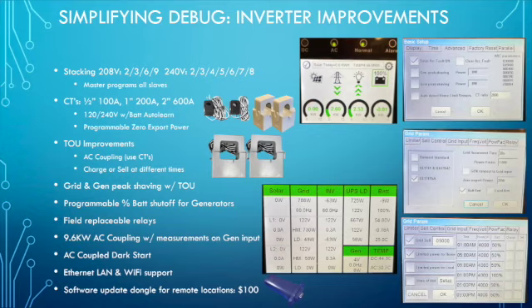So as far as inverter software improvements and other things, we did quite a few developments. We introduced stacking for 240 volt. That's been around for a while, and you can do anywhere from 2 to 8. But you can also stack 208 systems, and you can do 208 with just a single system. However, you won't be able to do all 3 phases, just 2 of the 3. So if you get 2 inverters and stack them on 3 phase, then you can hit all 3 phases, but they're not completely balanced, which is still fine from the utility standpoint. But if you do 3, 6, or 9, then it's completely balanced 208.